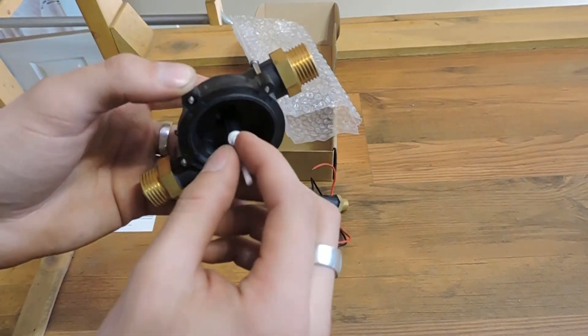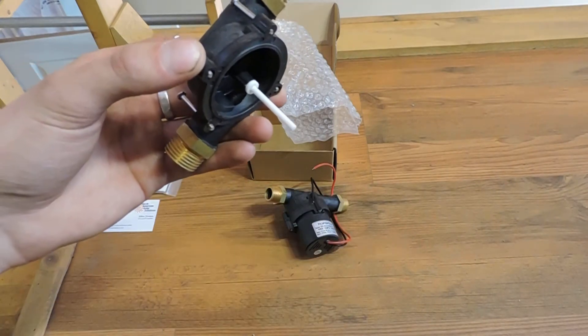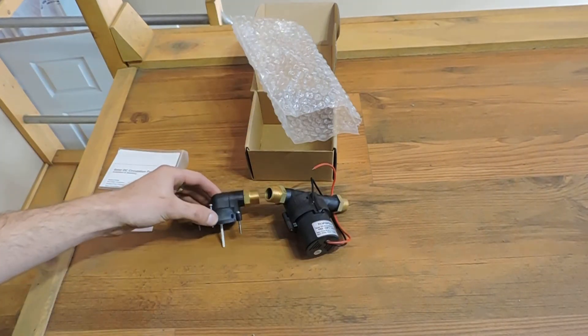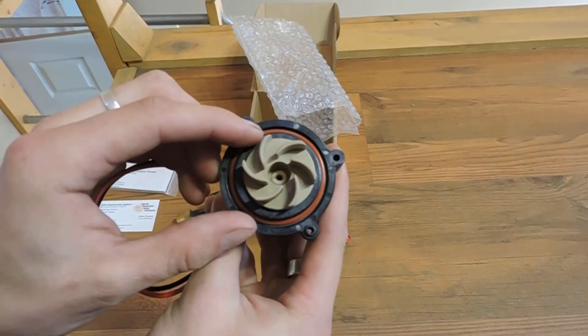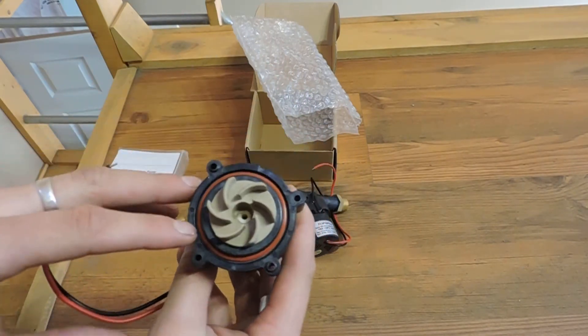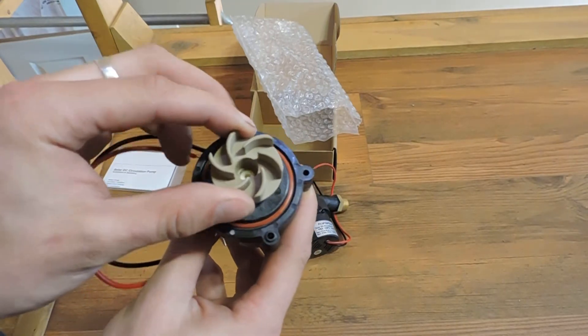On the inside you have a ceramic shaft. On the other side of the pump, you have your Viton o-ring. This one is especially made for glycol systems as glycol can eat away at standard seals.